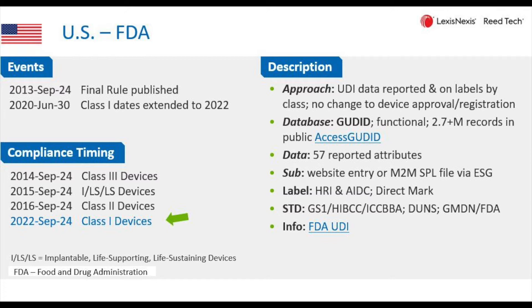As to the timing, the FDA started off with the high-risk devices first, requiring implementation on both the label and for the reporting of the GUDID data to the GUDID database. So Class 3s, implantables, life-supporting, life-sustaining, and Class 2s are all passed.